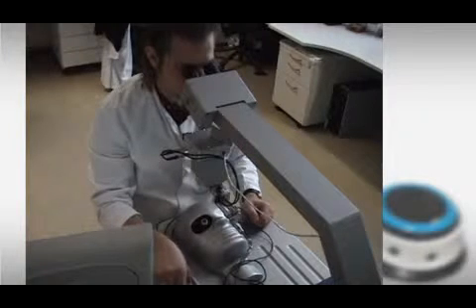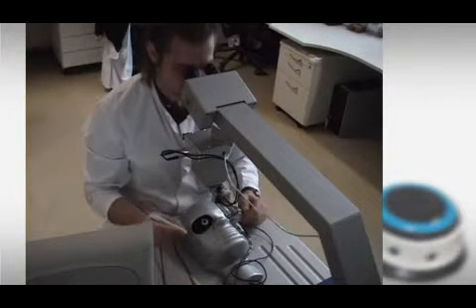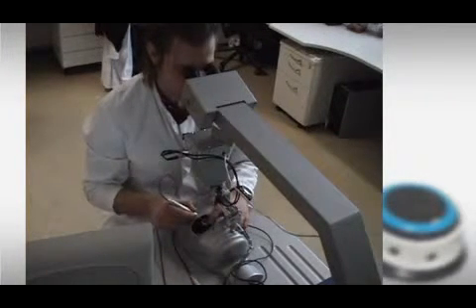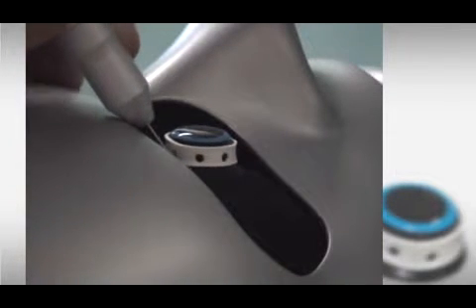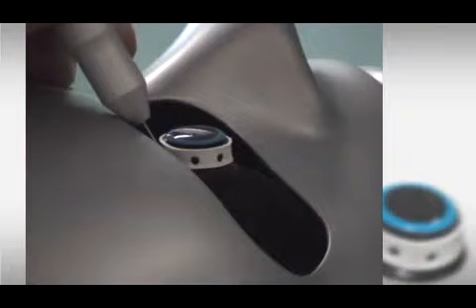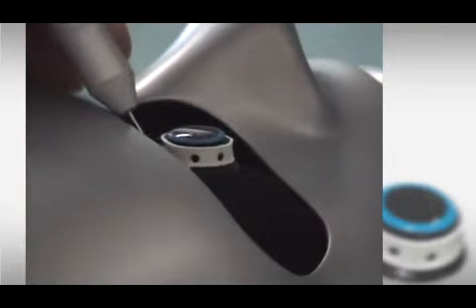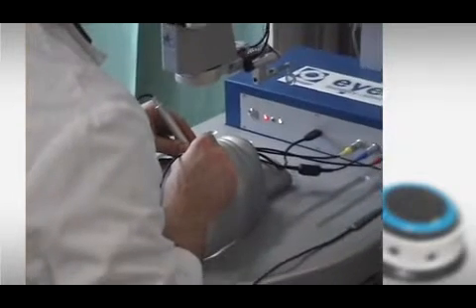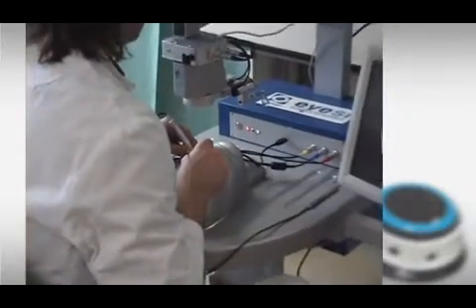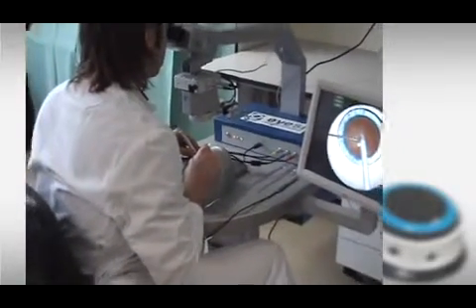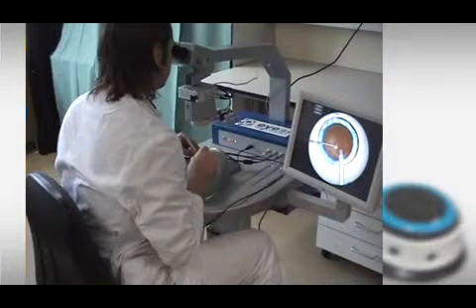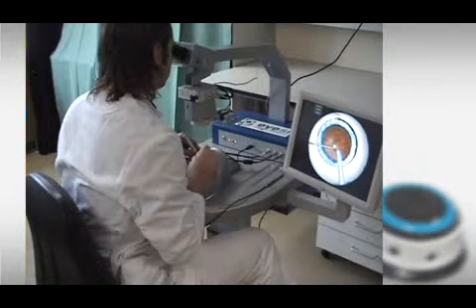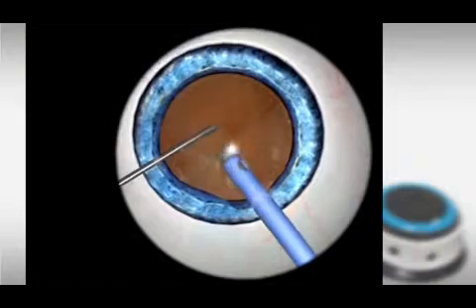The surgeon operates via a stereo microscope as in a real situation. After inserting the instrument into the artificial eye, movements are detected by optical tracking and transmitted to a computer that creates a virtual image, which is then presented via the stereo microscope in a three-dimensional mode, including visualization of the red fundus reflex.